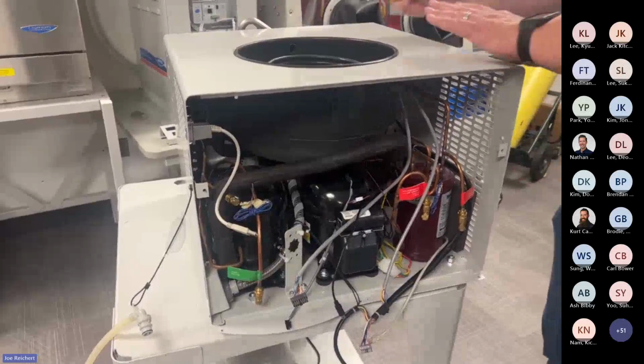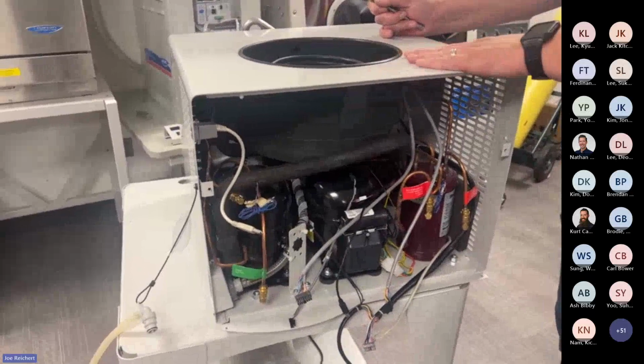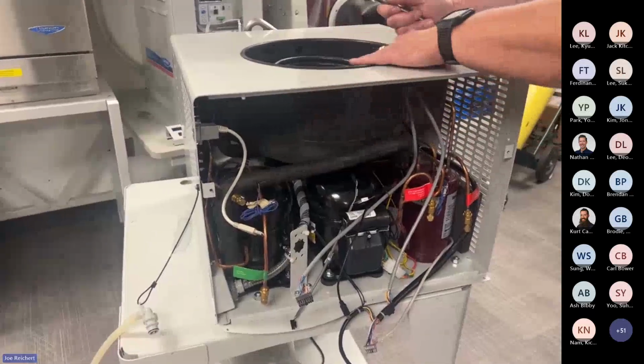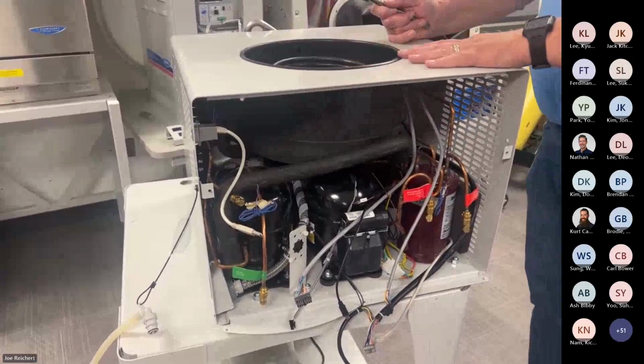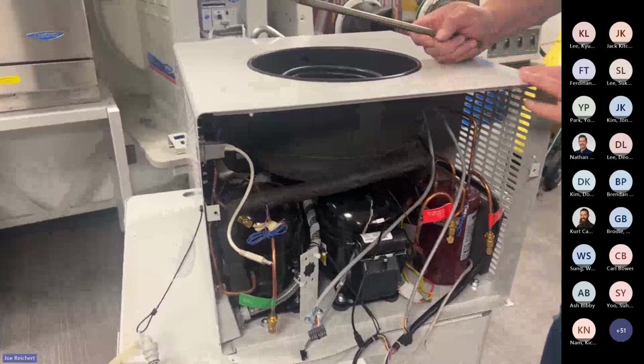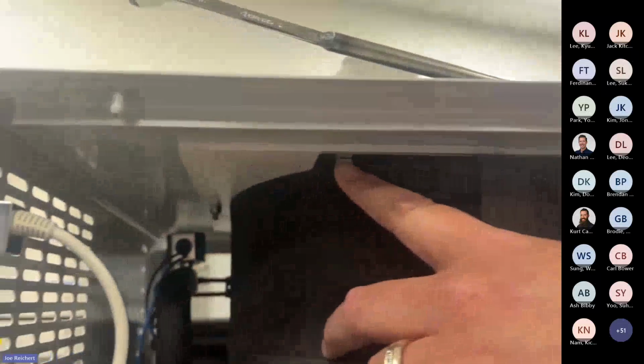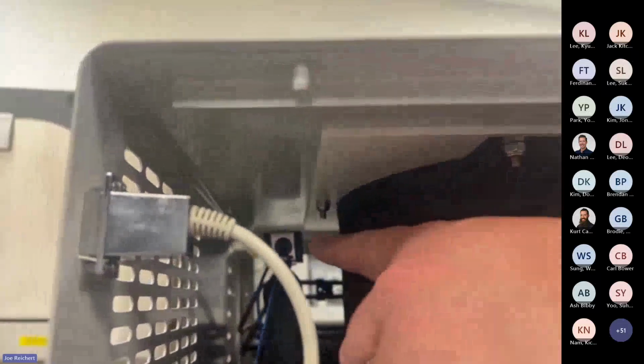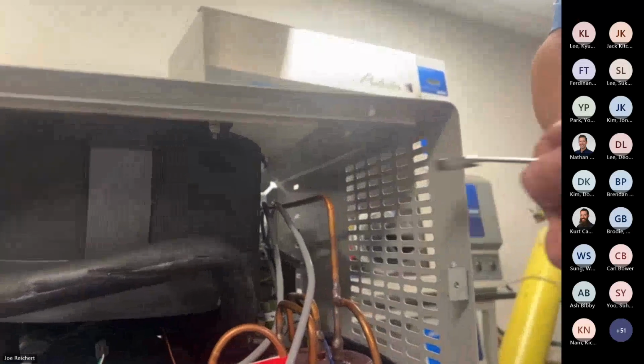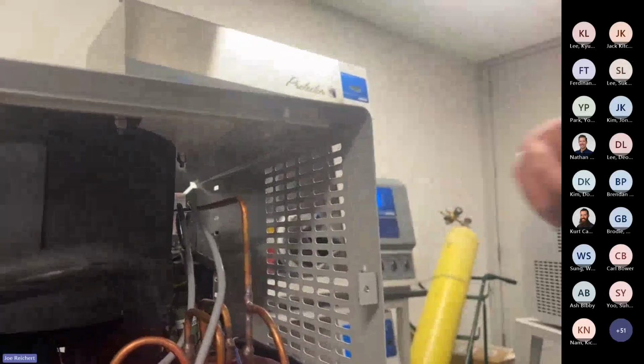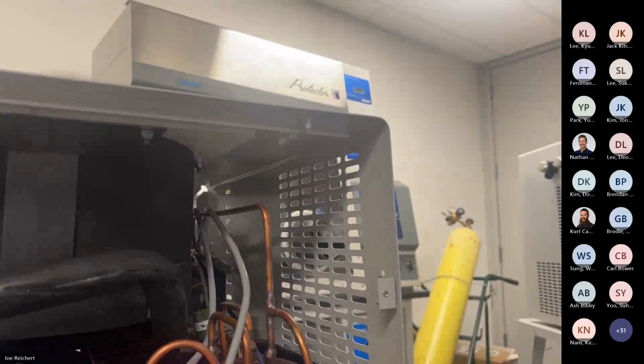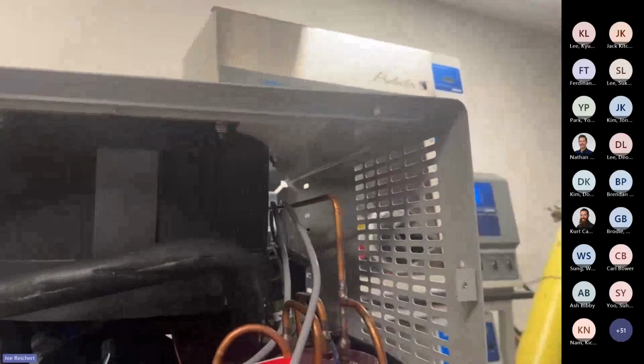So on the inside of this unit, to take the wrapper off, we've already removed all the screws from the side, but we have 6 screws that are attaching the chamber to the wrapper. If we look up inside here, right here in the front, 2, so there's going to be 2 in the back, and then there's 1 on each side. These side ones are the ones where this tool really works well for us to reach all the way back in here to get to it. So I will remove these. Trying to remember which way that goes.